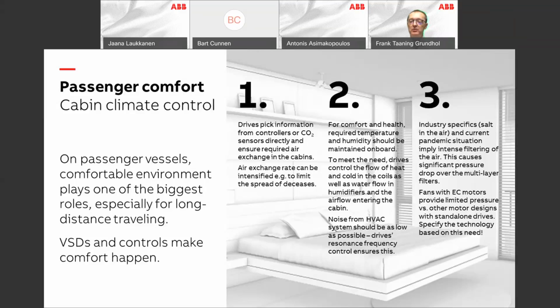There's been a lot of talk about sizing and reduction of sizing, and that's put some focus onto the EC fan side of the business. But EC fans have the disadvantage that they're single purpose - they can only be used for normal ventilation. So if you've got combined systems that also require smoke extract, they cannot be certified for that purpose, because the electronics internal to the fan wheel simply can't withstand the temperature requirements. In addition, very few of these are available with sufficient coating, which means the risk of corrosion is also higher.